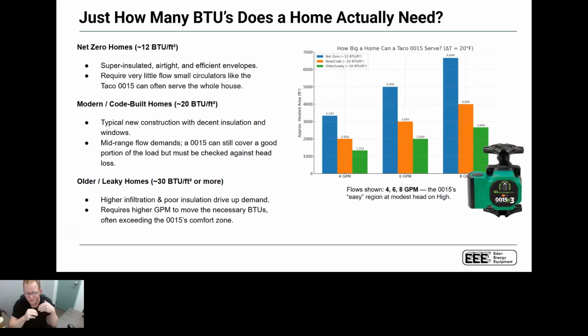But we've got to understand that, just as technology has evolved, so has the building envelope, so have the actual mechanical loads. In the same way, sensible and latent cooling loads are changing. So we want to make sure we're designing systems appropriately. This is not a conversation about flow rates and pumping, but we also have to understand that we can deliver a lot of BTUs in an air to water application with a single small Taco 0015 circulator. I chose the Taco 0015 because my good friend Dave Holdorf was doing training here today as well. A Taco 0015 can cover a really, really large home. At 8 gallons a minute, we can deliver a lot of BTUs out of this space.